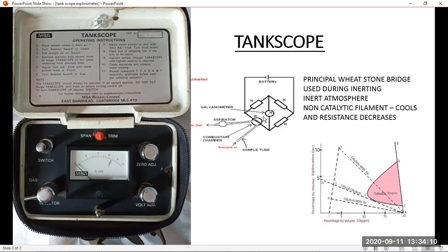So we need an element which is a non-catalytic filament, whose resistance changes without any burning. So this element is a non-catalytic filament, and as the temperature cools down, the resistance decreases. The resistance change is measured in the galvanometer through the flow of the current, and the reading of this galvanometer will be changing, indicating the percentage of hydrocarbon. So this is the use of the Tankscope while inerting.